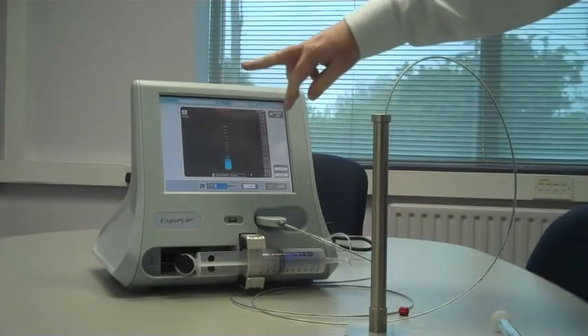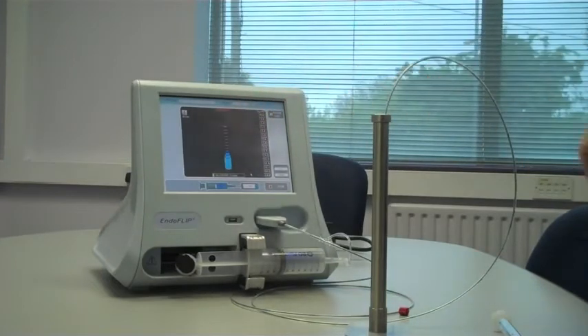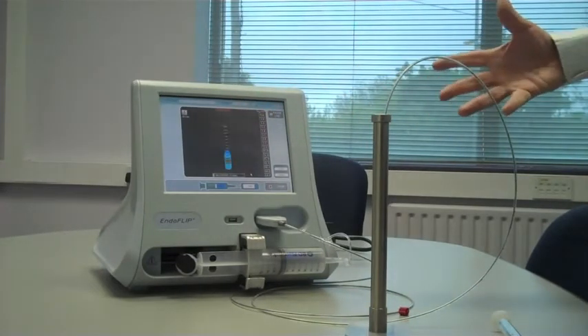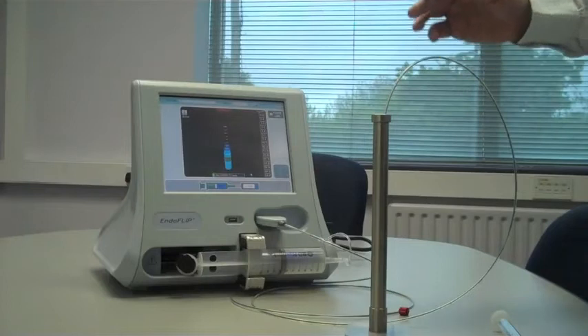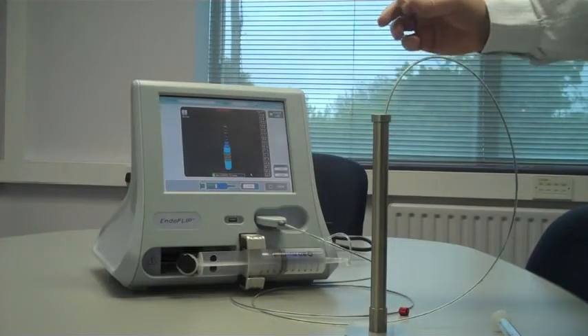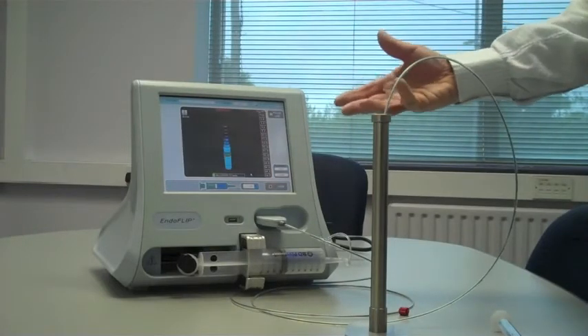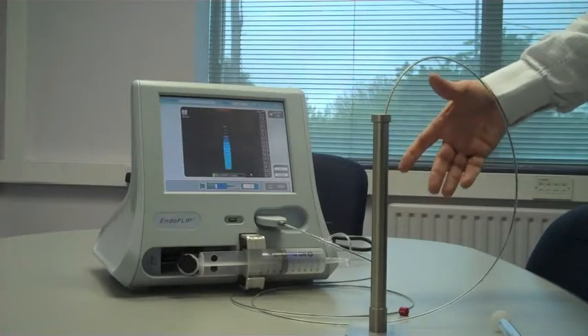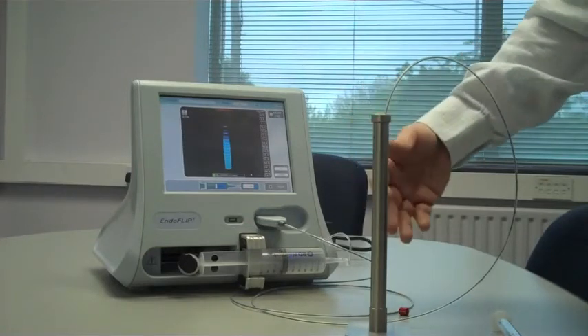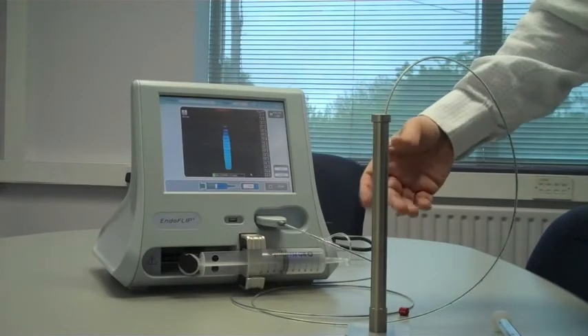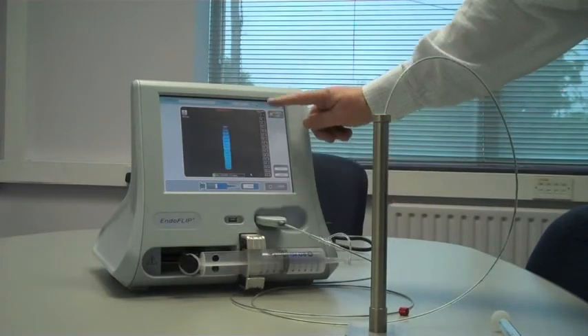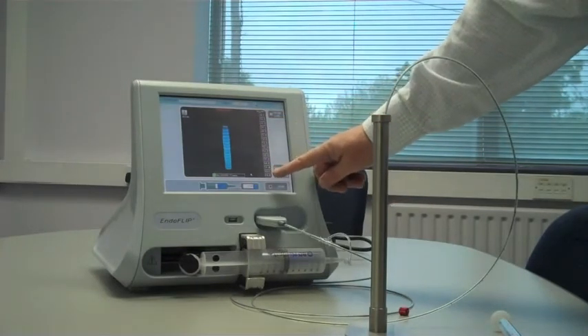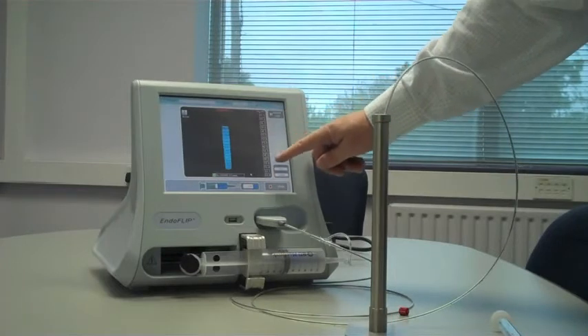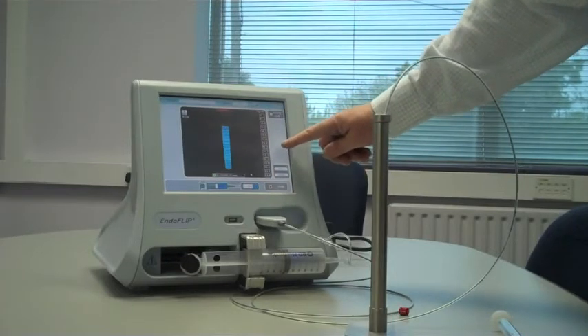Now sometimes you may see large variations in diameter while there's little fluid in the balloon. It's important that the full balloon has fluid in it, since the way the system works, the outermost electrodes drive a signal into the balloon and then the remaining electrodes read. So here we're getting a good degree of comfort. We can see that all the electrodes are reading around 14 millimeters.